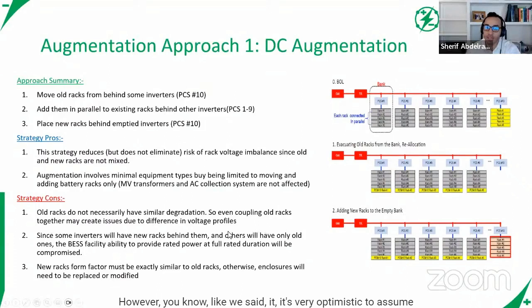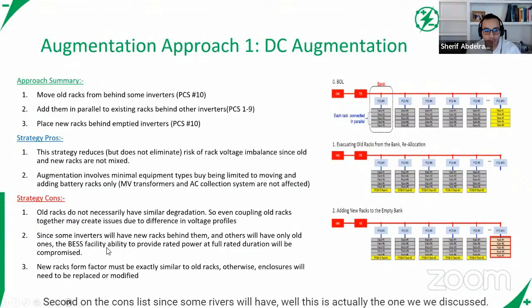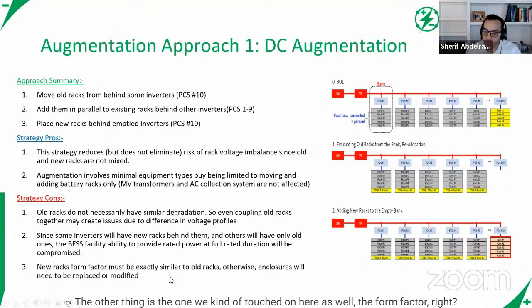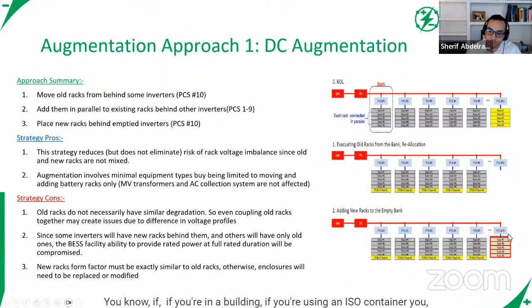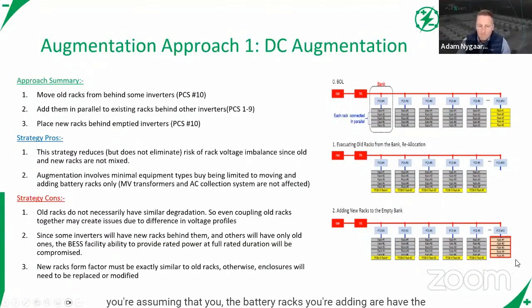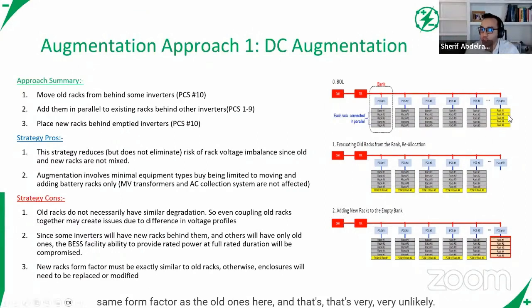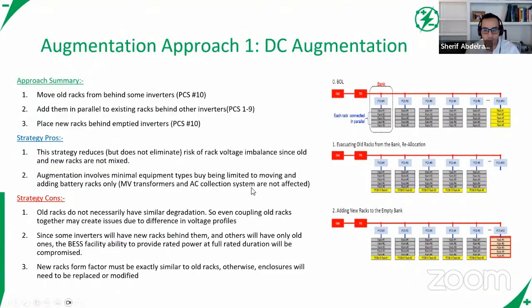However, it's very optimistic to assume you'll have the exact same voltage profiles across all old racks. Second on the cons list is the form factor - if you're in a building or using an ISO container, you're assuming the battery racks you're adding have the same form factor as the old ones, and that's very unlikely. So that concludes the first augmentation approach.